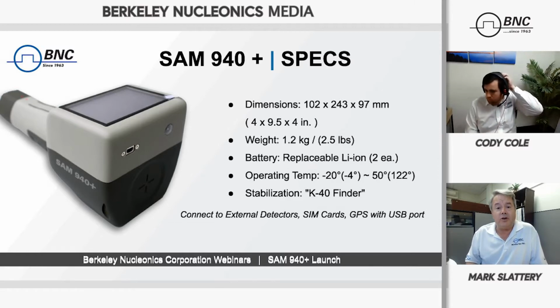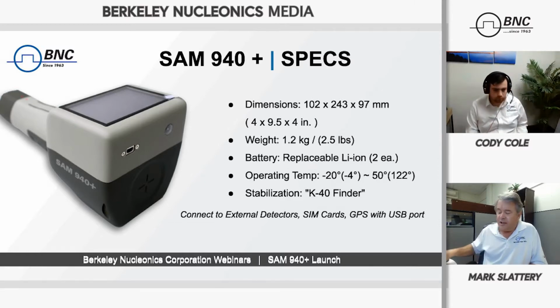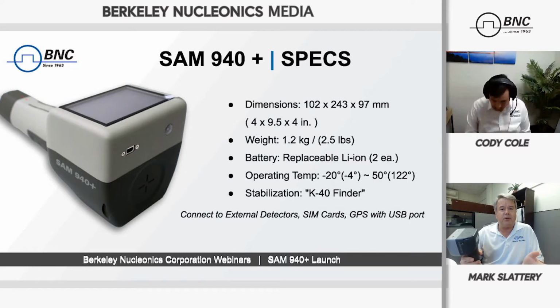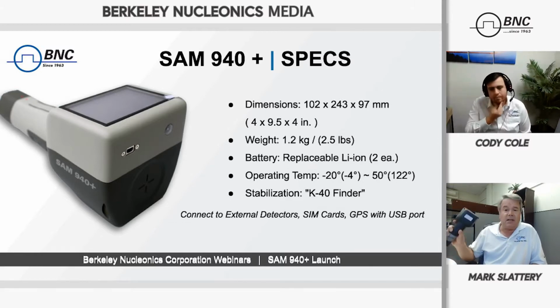The stabilization and auto calibration is performed without any onboard sources. The device uses an enhanced program for identifying or seeking out potassium-40 that is already in the environment. Potassium-40 is around us all the time - it's an easy one to find and distinctive. By searching in that area, it can identify the energy, enhance that signal, and perform its calibration of the scale on the SAM using the K40. So it is using K40, but it's not internal.